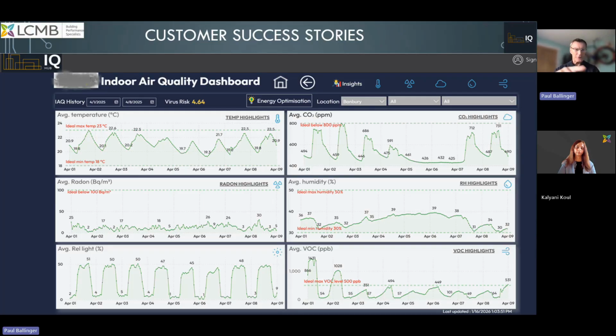Starting with the temperatures, the set points there, the two lines on the top and bottom were measured, and the company was looking at the dashboard to see where they went outside those set points. In the first 3 or 4 months, there were some quite scary dashboards that came out. They were heating areas where they didn't need to, and cooling areas that were inappropriate to be cooled at the time.